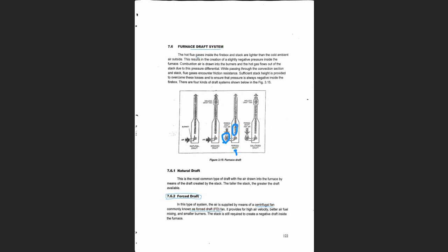جميل. طبعا the good thing about the forced draft يا شباب is that you can measure and control air flow rate. تقدر تقيس لأنك طبعا عندك كومبريسر لازم فيه suction pipe وdischarge pipe، صح ولا لا؟ وبالتالي you can install a flow instrument، آلة دقيقة لقياس الفلو ريت، ومن خلالها تقدر تقيس الفلو ريت. طبعا the disadvantage is that you have a compressor to force air to flow into the furnace or the boiler, and that means more operating and maintenance costs.